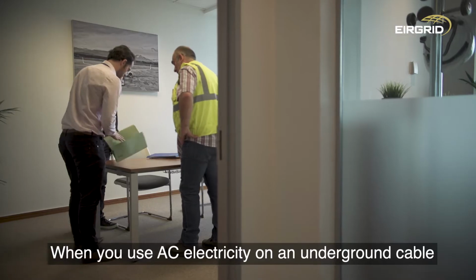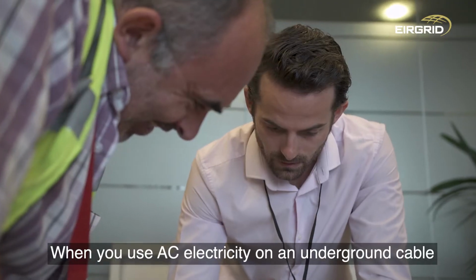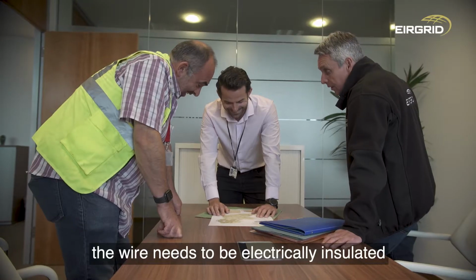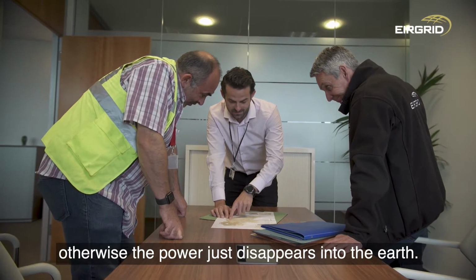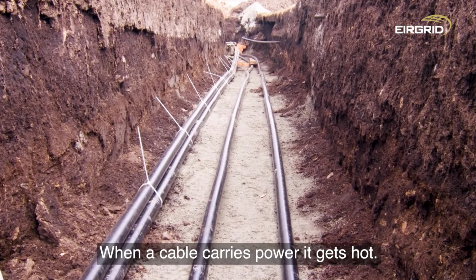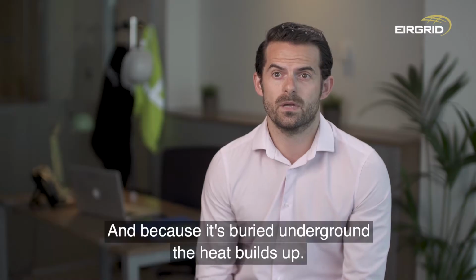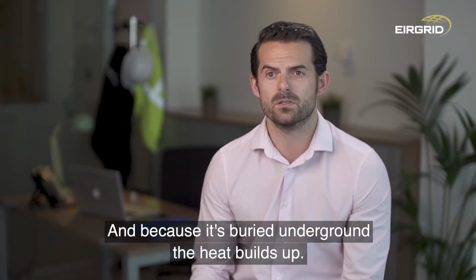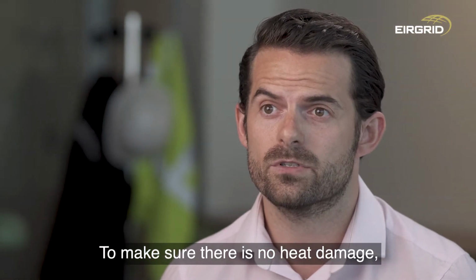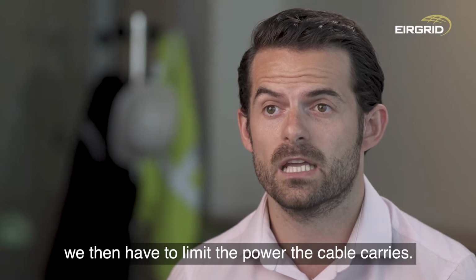we use it. When you use AC electricity on an underground cable, the wire needs to be electrically insulated, otherwise the power just disappears into the earth. When a cable carries power, it gets hot, and because it's buried in the ground, the heat builds up. To make sure there is no heat damage, we then have to limit the power the cable carries.